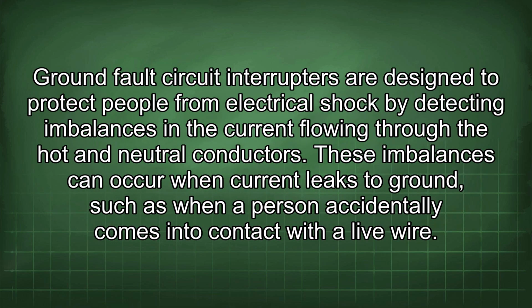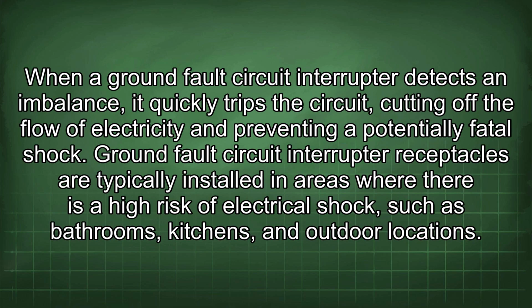Ground fault circuit interrupters are designed to protect people from electrical shock by detecting imbalances in the current flowing through the hot and neutral conductors. These imbalances can occur when current leaks to ground, such as when a person accidentally comes into contact with a live wire. When a ground fault circuit interrupter detects an imbalance, it quickly trips the circuit, cutting off the flow of electricity and preventing a potentially fatal shock.